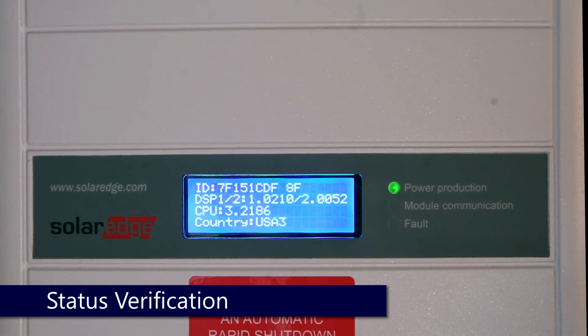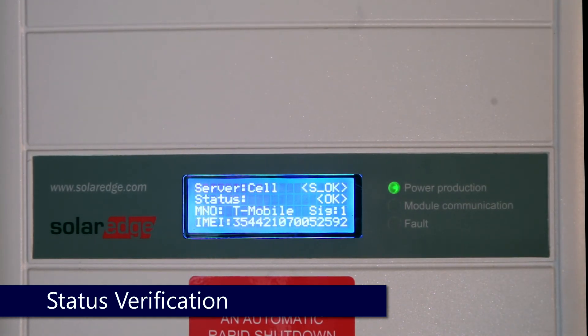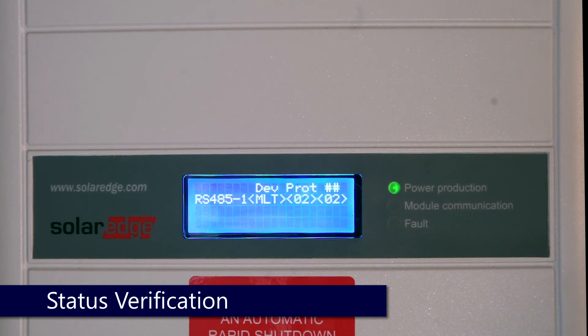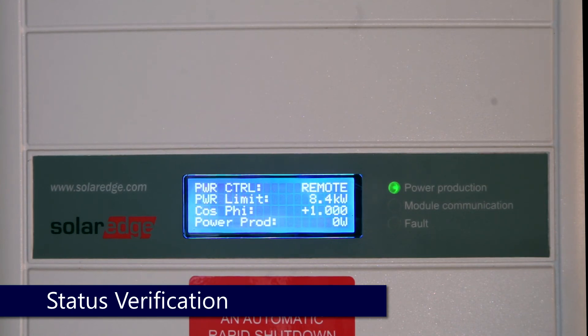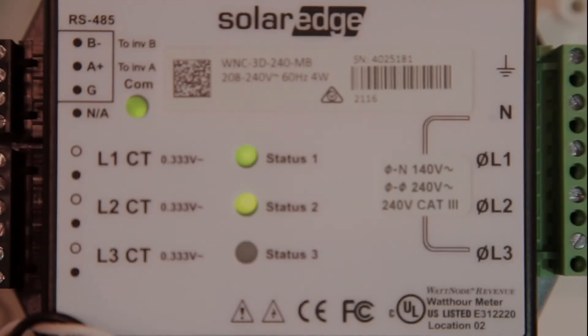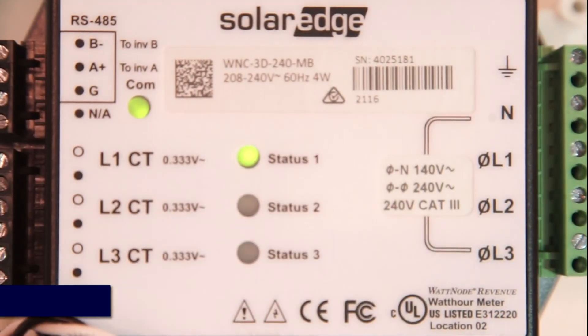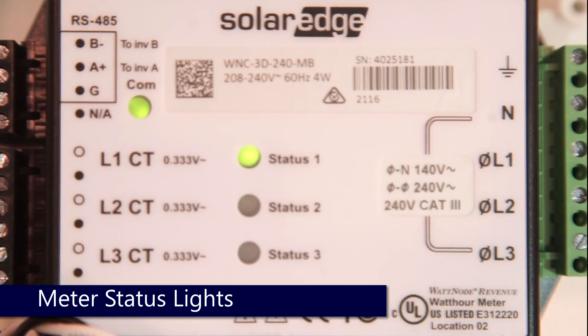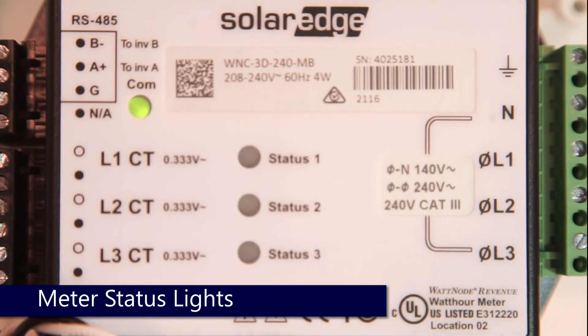Verify everything checks out and that we've got OKs on both meters. Then verify on your meter itself that the CT lights are blinking green and that we've got a green Meter Comm light. Thanks for joining us in the SolarEdge Learning Lab.